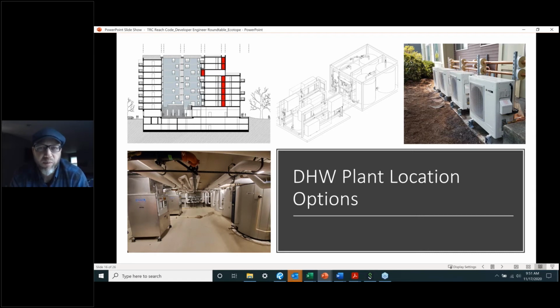They'll sort of blend in with the facade color and shape. But we have run into concerns for rooftop, and then for ground mount, and obviously in the basement those are tucked away in a room. It's not super clear in the photo, but we're actually discharging the spent air out of the heat pumps through a louver back into the garage, so there's a lot of air movement in that lower plant in the garage. I'll show some more details on that.